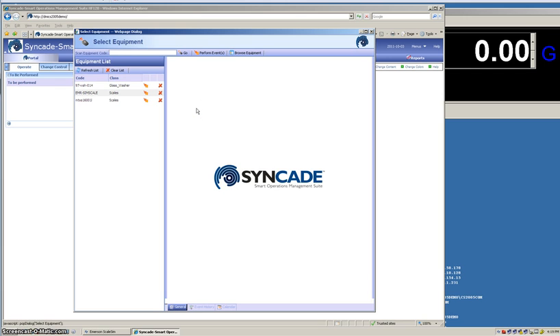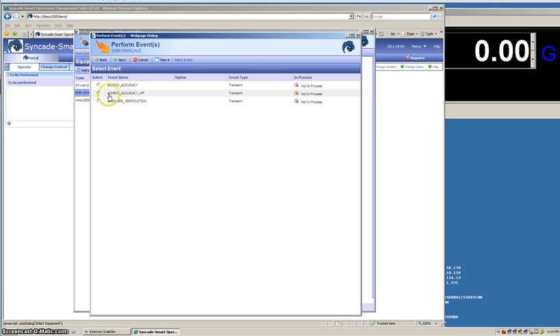the accuracy. Normally we would want to check the accuracy every day to ensure that the scale is within tolerance before using. We're going to click the lightning bolt there to execute an event, and the event choice that we're going to work on today is the check accuracy with workflow.